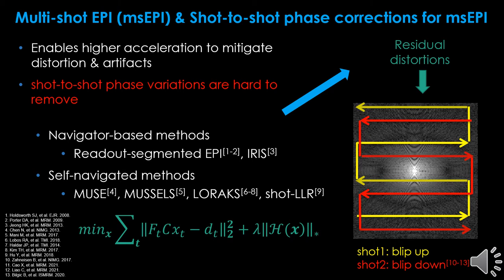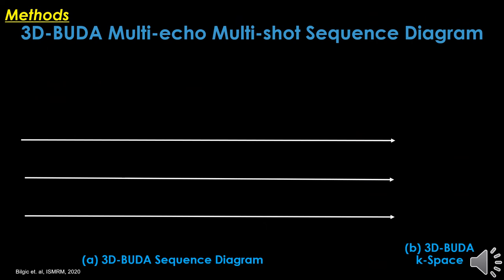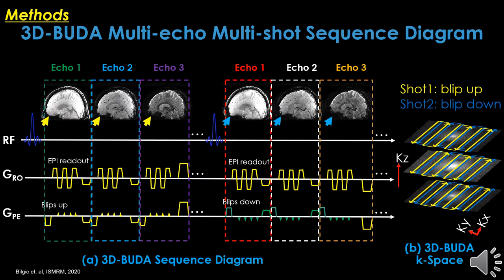They just neglect the residual distortions. Recently, a blip-up blip-down acquisition was proposed for further eradicating the distortions. Instead of obtaining two shots with the same polarity, they acquire the shots with inverse polarity, aiming at totally solving distortion issues. Similarly, we propose the BUDA technique for 3D readout with both single-shot cases in blip-up and blip-down.